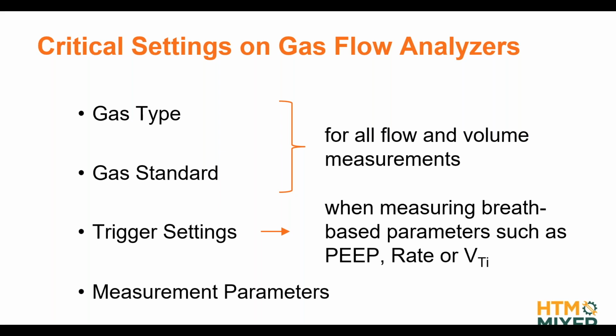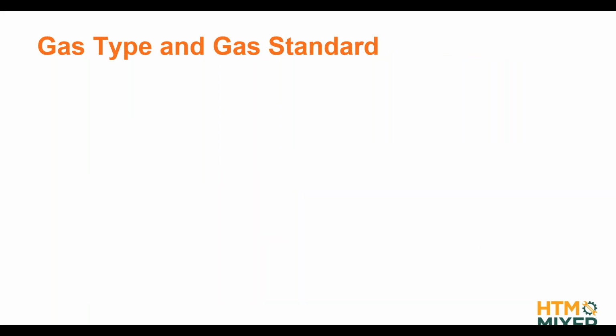And then the last settings we are going to talk about is the measurement parameters themselves. So gas flow analyzers can measure many different parameters, and it's important that we understand, okay, which parameter do we have to look at? What does it mean on the ventilator? And it's also important that we have it set up, for example, in the right unit of measurement that matches the ventilator. Okay, first we're going to dive a little bit deeper in topic of gas type and gas standard. So why do we need to set a gas type and gas standard on our analyzer?